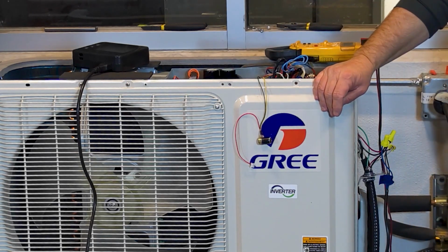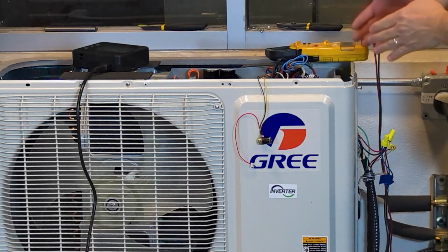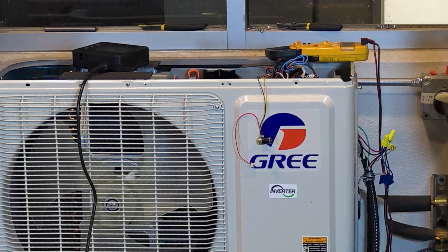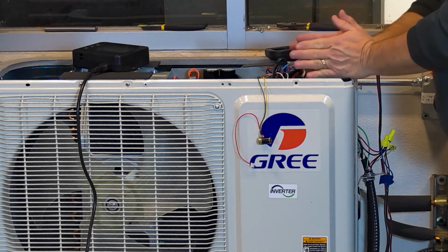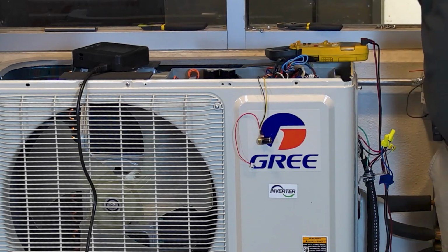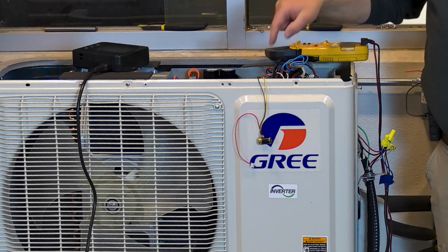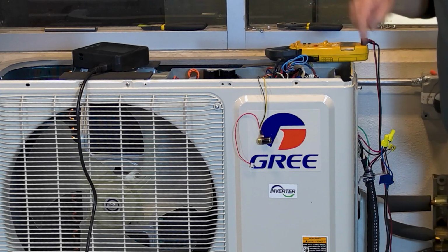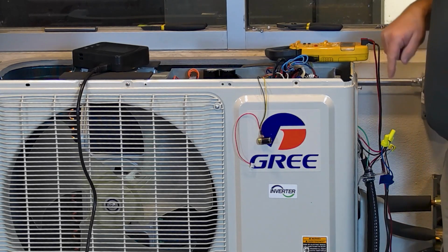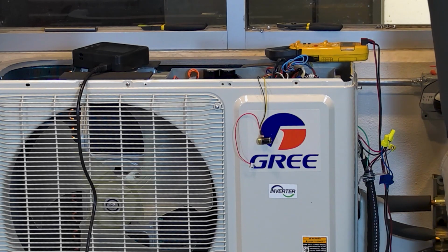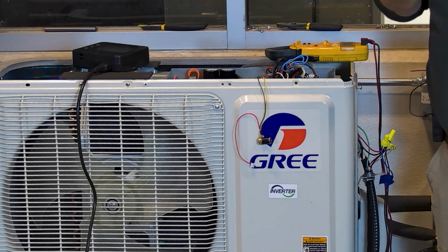And we'll demonstrate it for you. What JD was saying is, I can hook this service tool up, and I can disconnect the indoor unit communication wire. I can hook up to the outdoor unit, and I can simulate an indoor unit, and this machine will come on and run. I can hook up from the wires out here, disconnect my 2-wire going inside, hook up the service tool to the 2-wire going inside, and I can simulate the outdoor unit and make that machine run, provided the wire between them is good.